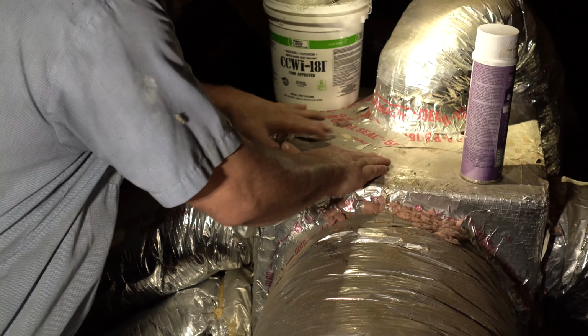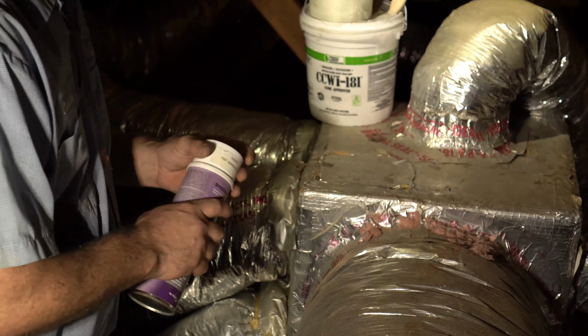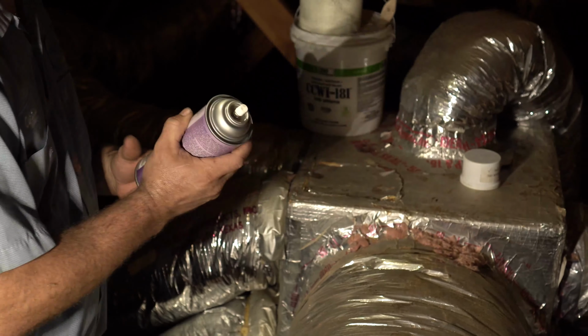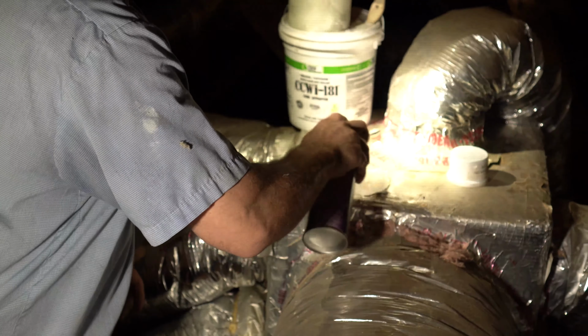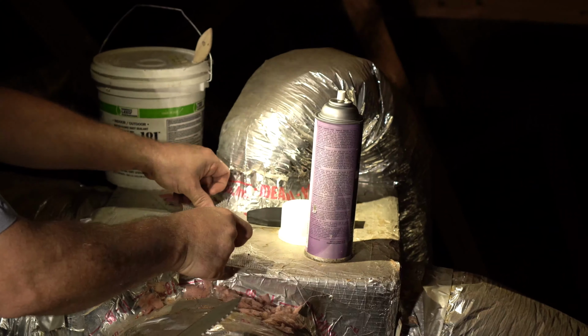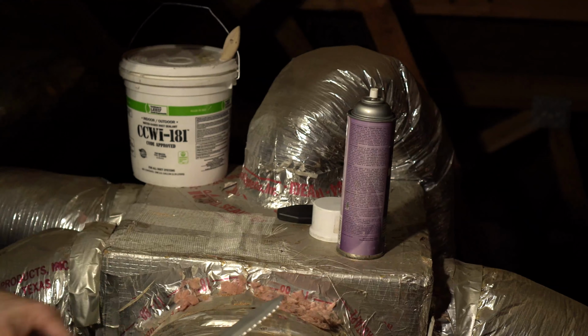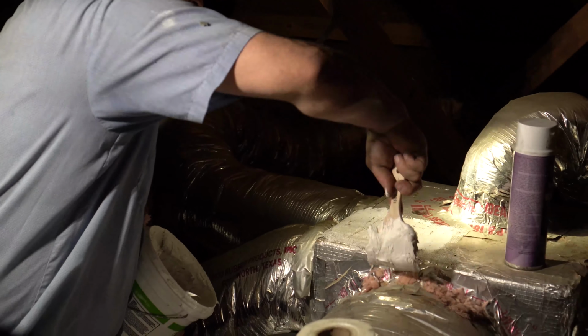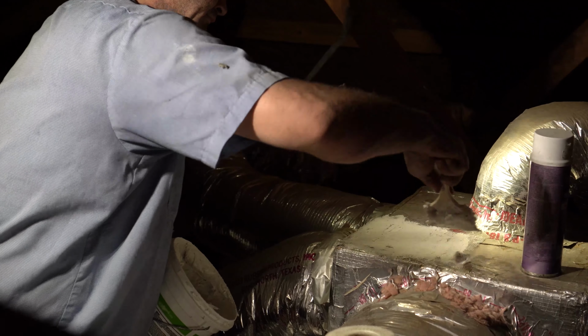It is important that you properly seal your duct penetrations. Weather Engineer's standard operating procedure requires you to use an approved duct sealing tape, glass fab, and mastic. If the duct system is dirty and dusty, a trick is to spray insulation adhesive on the surface to ensure tape will stick.